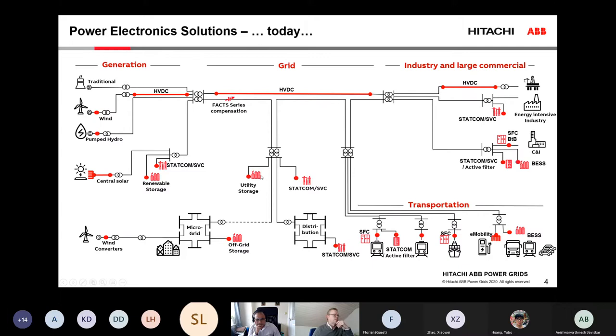And most of these new converters are based on voltage source converter technology. There we force the switching, so we can use a very high bandwidth of the control if we need to. This means that sometimes we do control in the same frequency range where we have resonances in the grid. And this can result in problems if it's not properly managed.